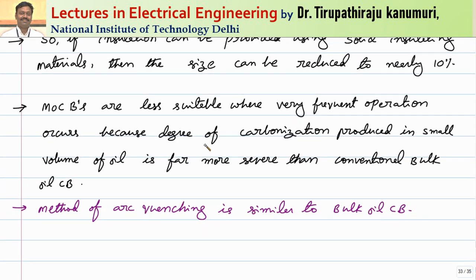There is a disadvantage of the minimum oil circuit breaker compared to the bulk oil circuit breaker. Every time an arc is produced, the oil decomposes and carbon is produced through carbonization. This carbon mixes with the oil and the oil loses its dielectric property. For example, assume 1 kg of carbon is produced per fault. In a bulk OCB with 100 liters of oil, 1 kg is mixed in 100 liters. But the minimum oil circuit breaker has only 10 liters of oil, so 1 kg of carbon is mixed in only 10 liters — the oil spoils at a much faster rate.